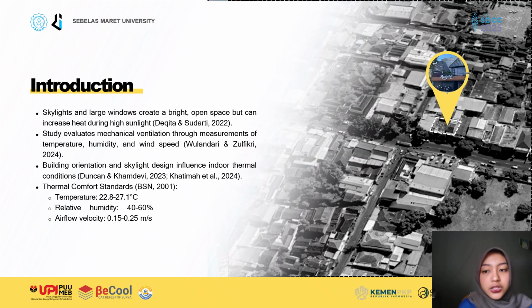According to the Indonesian national standards, the recommended indoor temperature range is 22.8 to 27.1 Celsius, with an ideal relative humidity level of 40 to 60%. Meanwhile, the comfortable airflow velocity is suggested to be within 0.15 to 0.25 meters per second.